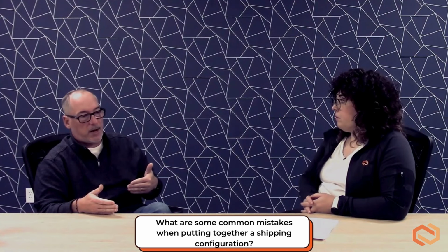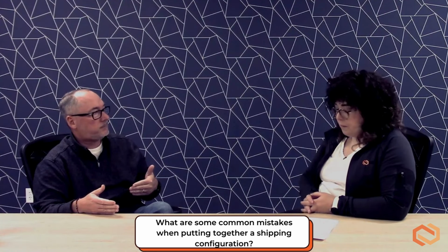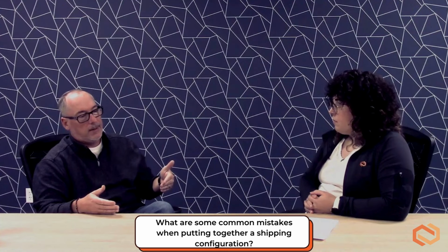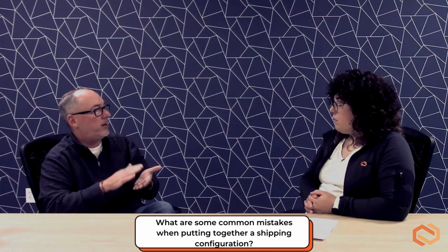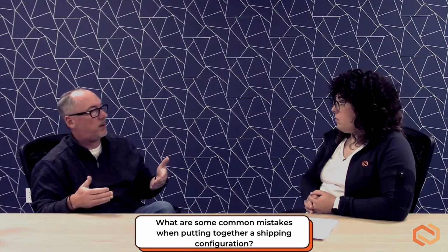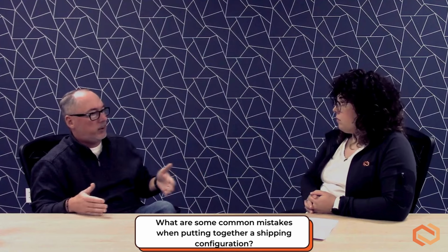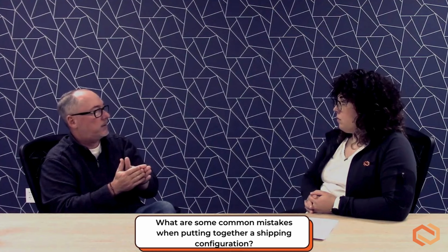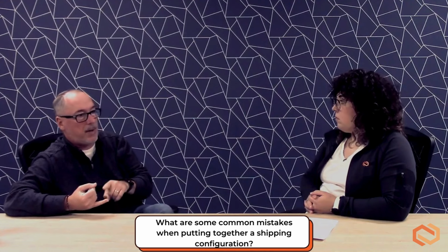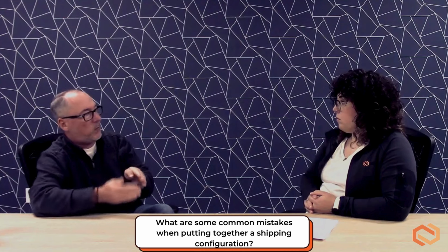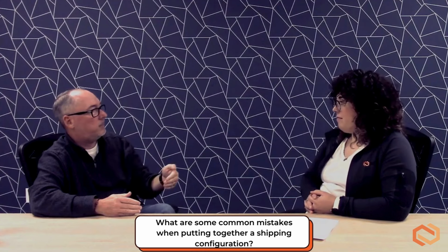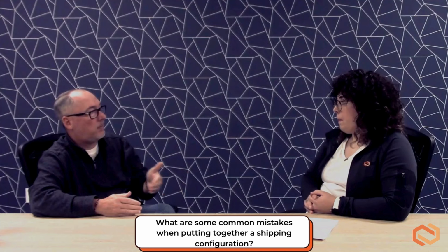Sure. The other aspect I see is the folding of the pouches, right? Folding of pouches inside, whether it is just a corrugated box or not, you're breaking the fibers. You're breaking the fibers of the Tyvek, or bending the fibers, I should say, as well as bending whether it's Mylar, nylon, etc. You're running into issues with abrasion of the product. Here's a prime example. We're dealing with a backer card, a backer card in a pouch. The pouch is folded. The backer card is moving back and forth inside the package, creating a hole. A very small hole, but a hole nonetheless.